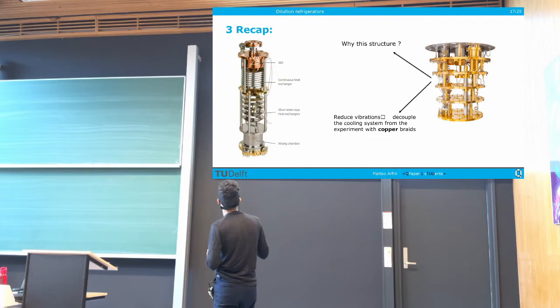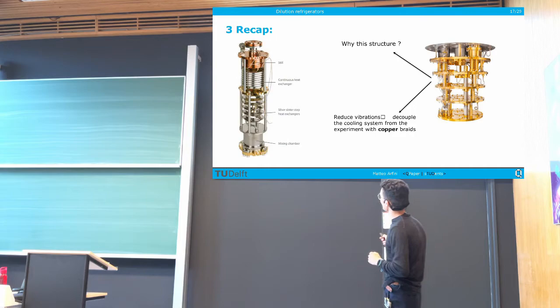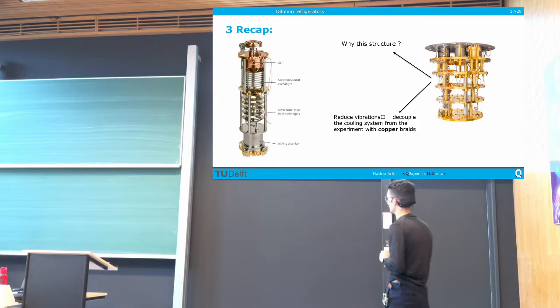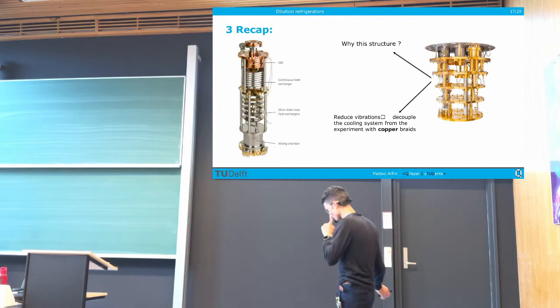Here you can see an actual real device. We have the still at 0.7 K, then a series of continuous heat exchangers down to around 20 mK, then a series of silver step heat exchangers to reach the very low millikelvin temperature range, and here the mixing chamber where the cooling power is achieved.